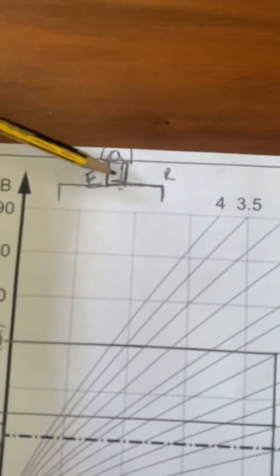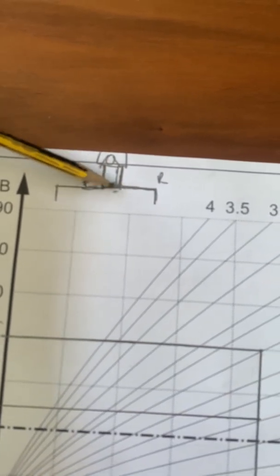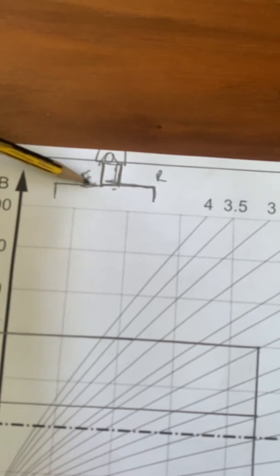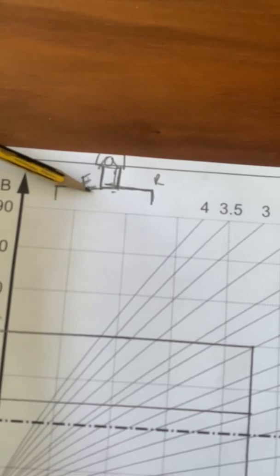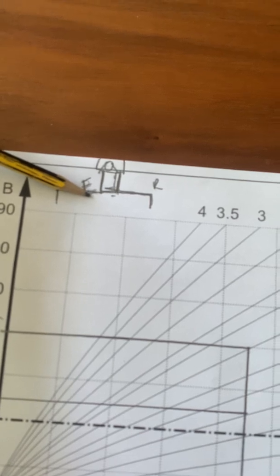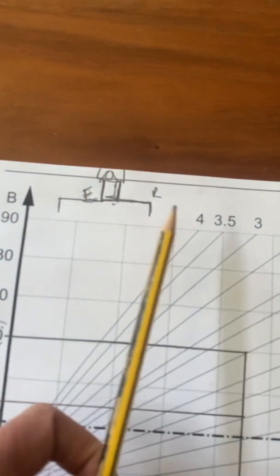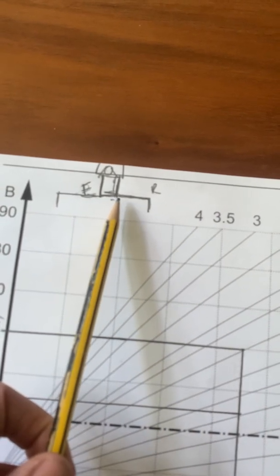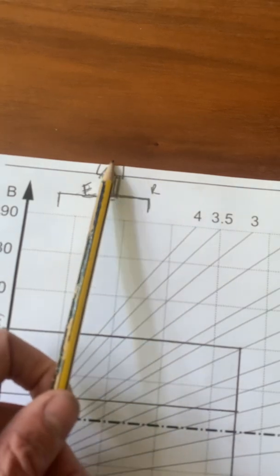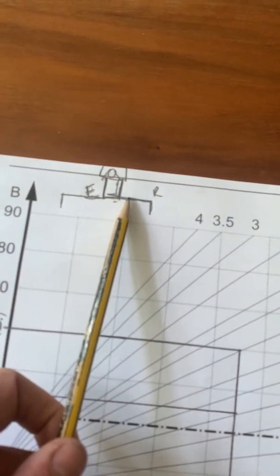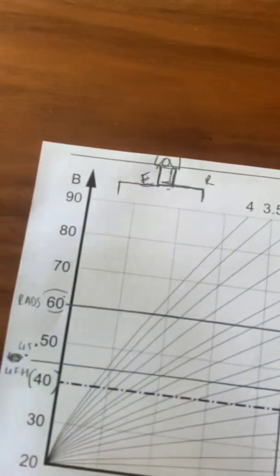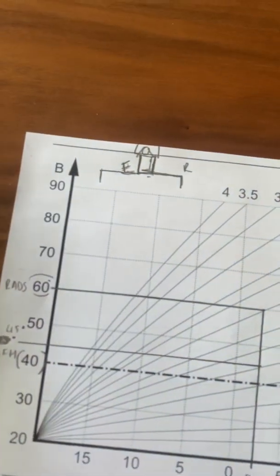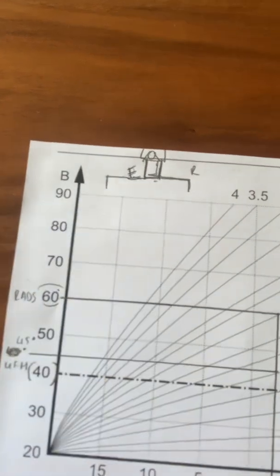It may not do that because we have the close couple T's and you might get some mixing here. The boiler knows this, there is a sensor here, and the boiler can sense what this temperature is. So if we're getting return water in and it's slightly more flow than the boiler, we will get some return water come across into here which then cools the flow down. Perhaps the boiler may actually be running at five degrees more, or a number of degrees more, and that's where it's not so good having separation, but necessary evil.